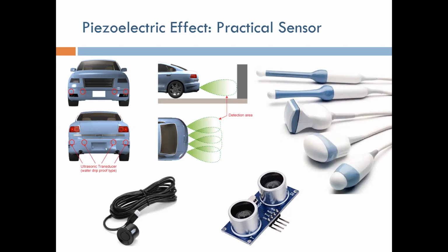Meaning that if you want to, for example, sterilize one of these transducers, common sterilizers use heat and steam, high pressure steam, basically to sterilize. If you use such techniques on ultrasonic transducers, they will not be ultrasonic transducers, basically. So they are going to be clean, but they are not going to be ultrasonic transducers. You're not going to be able to use them any longer, okay? And these are really expensive.